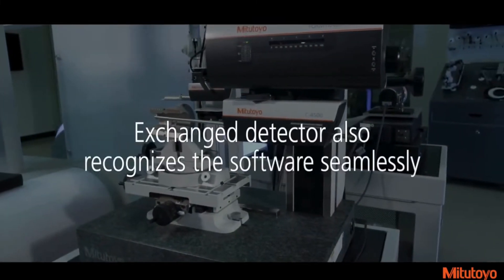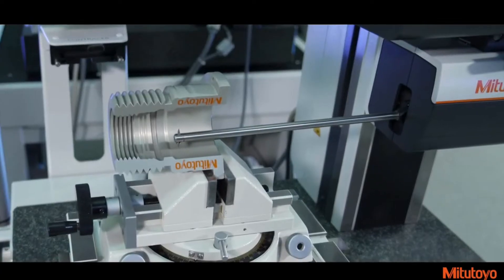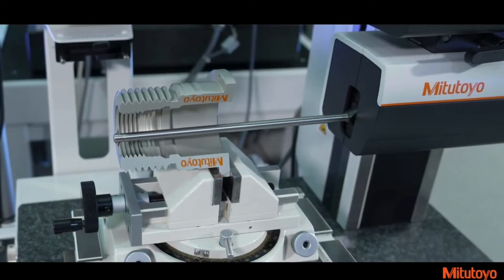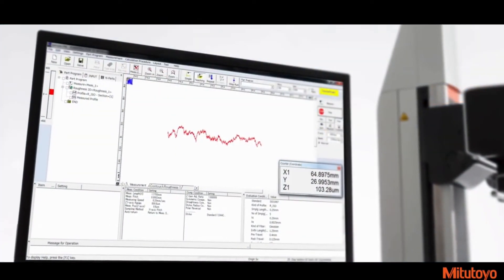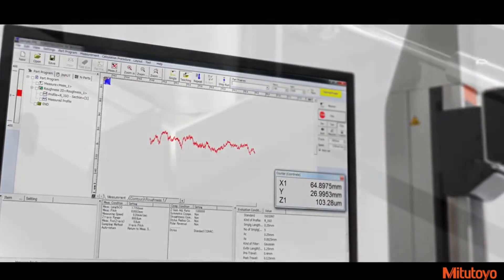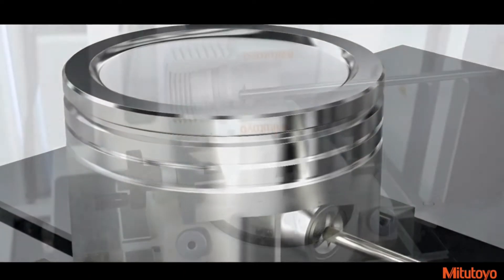The exchanged detector also recognizes the software seamlessly. The C4000 detector offers a new stylus protection function, which controls the downward movement of a stylus. Utilizing the current Mitutoyo Form Trace Pack software, the downward motion is slowed so the stylus can be detected when dropping off an edge during measurement. This reduces the risk of damaging the stylus tip.